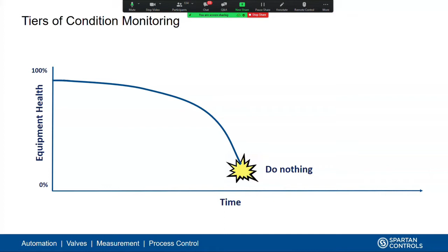What we're seeing a lot of people do now is install 4 to 20 milliamp overall vibration transmitters on the asset. So at least now we're measuring vibration, and vibration is a very good indication of asset health. As soon as we start to get a fault, the vibration we measure on the asset will increase, and eventually increase to the point where the asset fails. So by monitoring that vibration and bringing that information into our SCADA system or PLC, at least we get some warning that something is happening with that pump.